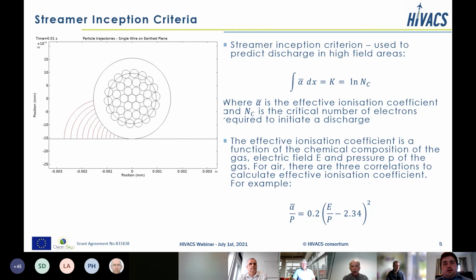Streamer inception criteria, I've already been through this in the previous presentation, but very quickly you can see here that in the image we've got the electric field contour lines, and we evaluate this equation along these lines until we get a value of 6 for the variable K, and this is our partial discharge inception voltage.